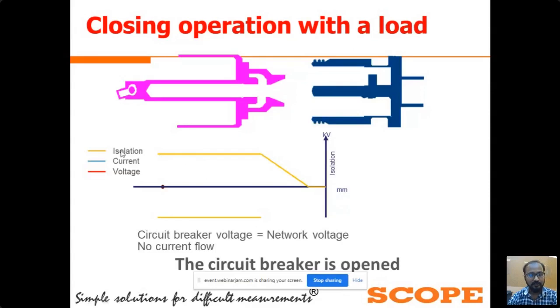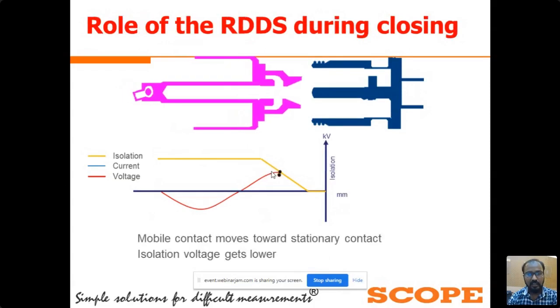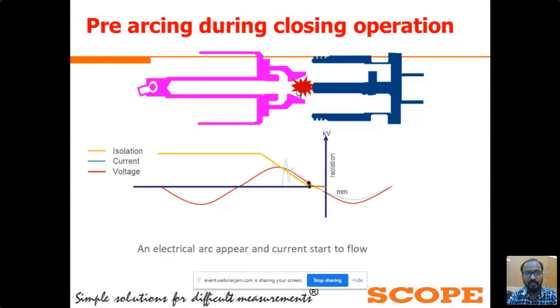Here you can see, this orange graph is the dielectric strength between the CB contacts, and this red sinusoidal waveform is the voltage waveform. This is the system voltage waveform. Once we execute the command to the circuit breaker, at this moment the dielectric strength between the CB contacts is less than the system voltage. So at this moment the arcing current starts to flow between the CB contacts.